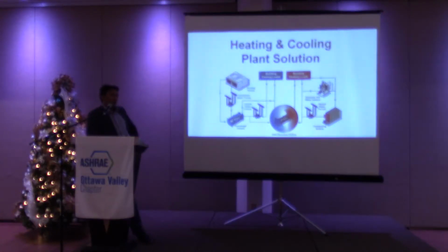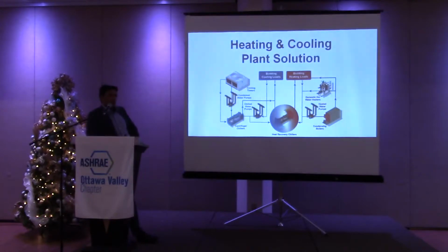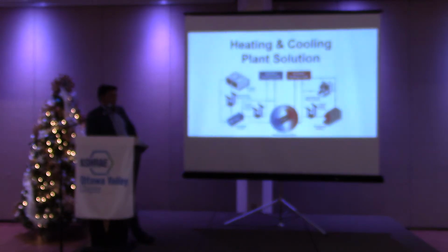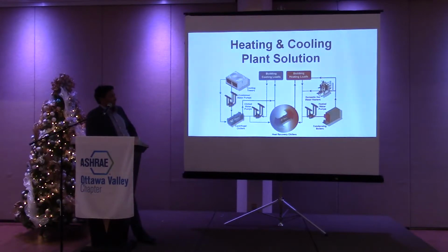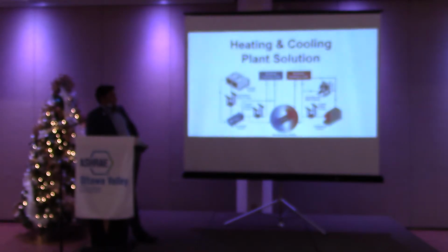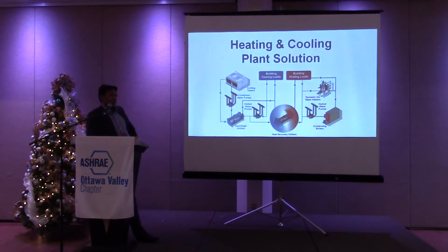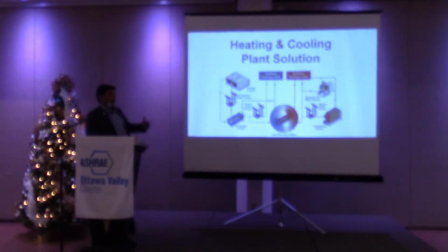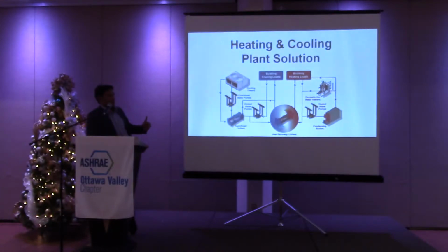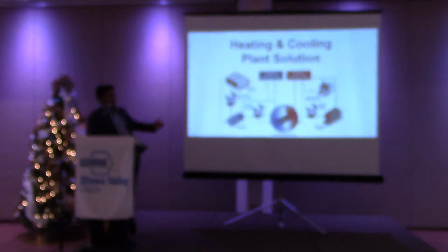So the CSA standard Z317.2 requires that we have a minimum number of air changes in all our healthcare spaces. In a patient room, it would be 6 air changes per hour. In an OR, it would be 20 air changes per hour. And we have to maintain those airflows regardless of space temperature. And so the way that we do that is we're supplying the same temperature air to all the spaces, but each individual space has its own reheat coil, and we're reheating to meet the space condition. What that means is you're actually heating even in the summertime. So you have this reheat demand all year round.